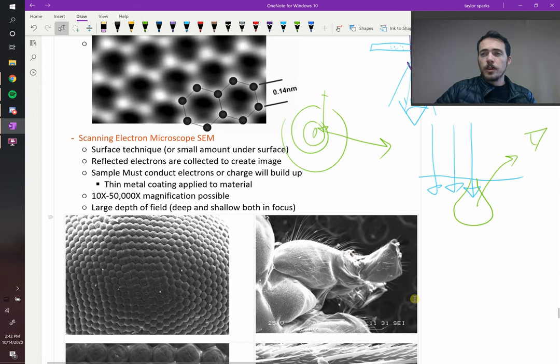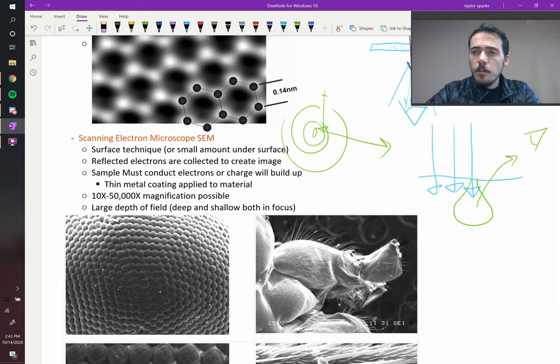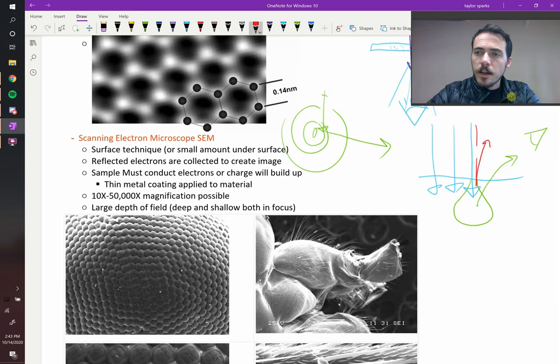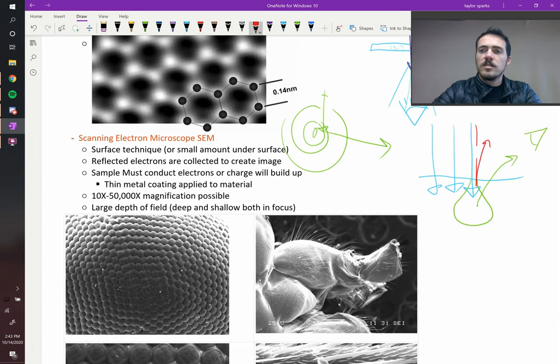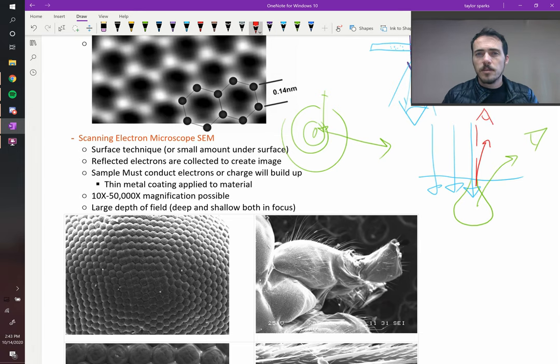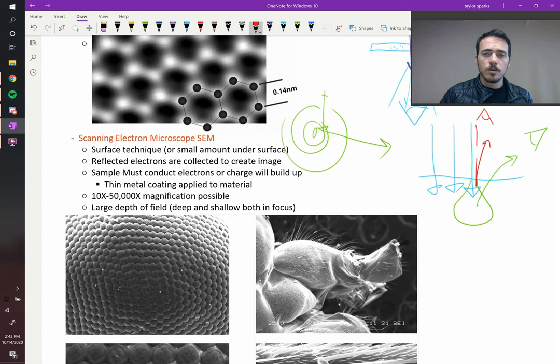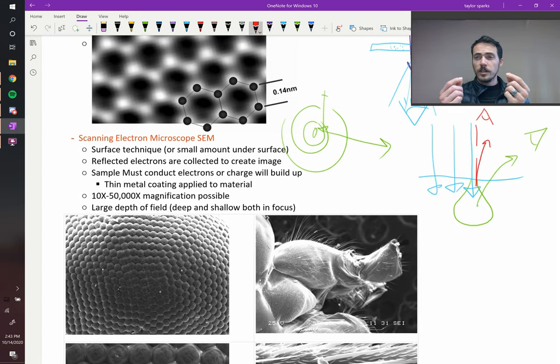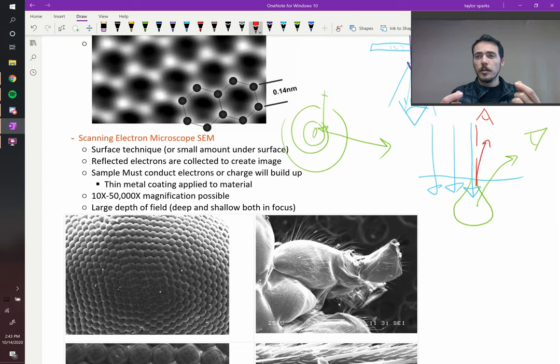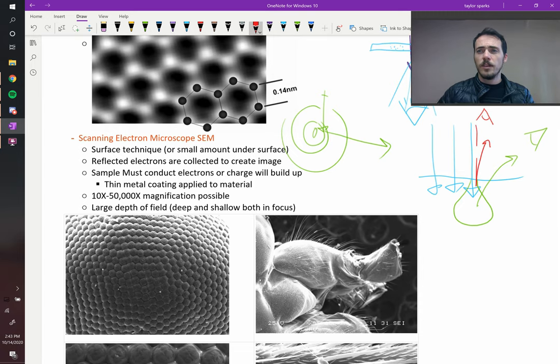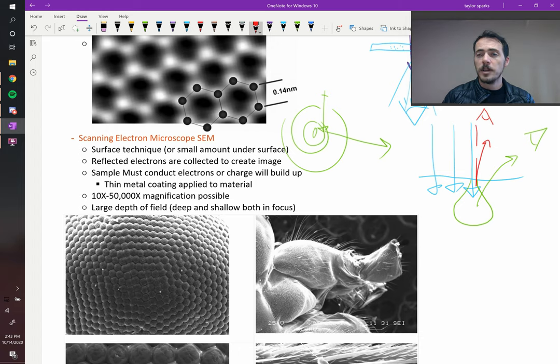But you can do other really cool things with it. Instead of just collecting the secondary electrons, the ones that come out of your sample, you can look at how many come in and then bounce right back off. We appropriately call those backscattered electrons. Those are the ones that hit nuclei, and so they bounce right back up. And so you have a sensor essentially right above your material so you can see how many bounce back. This is great because materials that have a high atomic number are going to bounce back more often. They're going to get more contrast than those that have low atomic number. So it's a tool that allows you to look at, you know, aluminum and steel might look really similar to our eyes because we just see the light reflecting off of it. But if you had backscattered detectors in your eye, then you'd see that, oh, iron is much more higher atomic number than aluminum. And so it's going to bounce back. And so it's going to appear brighter. Totally cool ability that augments how we can analyze material analysis. We've already talked about EDS, energy dispersive spectroscopy earlier. But that's a really cool thing for figuring out exactly what elements are present and mapping them.